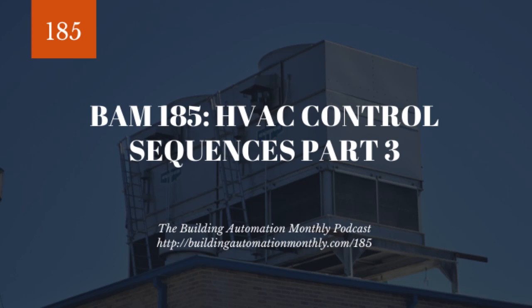That's what it's called. Now, we utilize this because when we are using constant air volume systems, we're not going typically for 55 degrees and hitting saturation and then allowing the air to mix once it actually gets to the space. We want to go and provide a constant volume of air, and we are hoping to control discharge air and sometimes even humidity at a constant volume unit. So we're focused in on that. When we're dealing with these type of units, we'll typically have cooling and we'll typically have reheat. Sometimes we will not see reheat at a mixed air single path variable air volume air handler, because we will depend on the terminal units downstream to do reheat at the space and zone level.